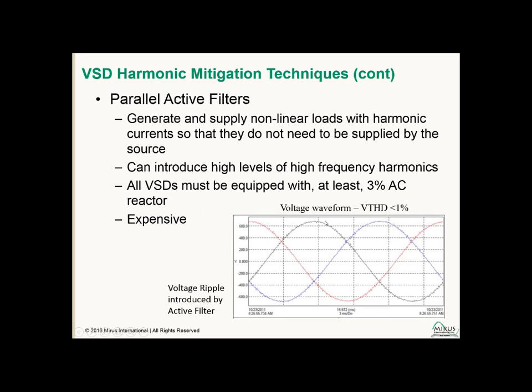And that high frequency voltage was causing a power supply in a tester at the facility to burn up as soon as it was energized, as soon as it was turned on. That power supply was resonating at this ripple frequency and therefore overloading and overheating. The only solution at the site was to turn off the parallel active filter to prevent those failures.